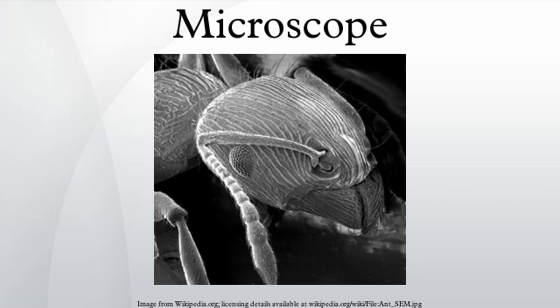Typical magnification of a light microscope, assuming visible range light, is up to 1250x with a theoretical resolution limit of around 0.250 micrometers or 250 nanometers. This limits the practical magnification limit to 1500x. Specialized techniques may exceed this magnification, but the resolution is diffraction limited. The use of shorter wavelengths of light, such as the ultraviolet, is one way to improve the spatial resolution of the optical microscope, as are devices such as the near-field scanning optical microscope.